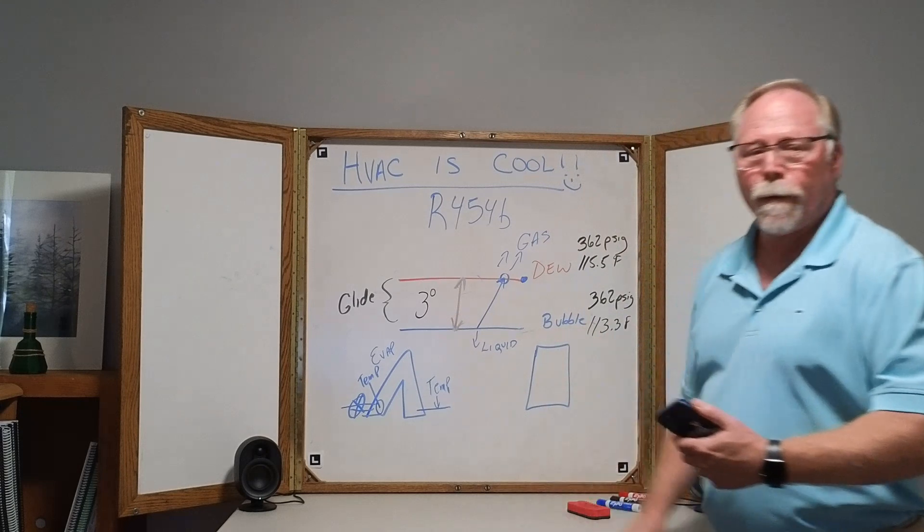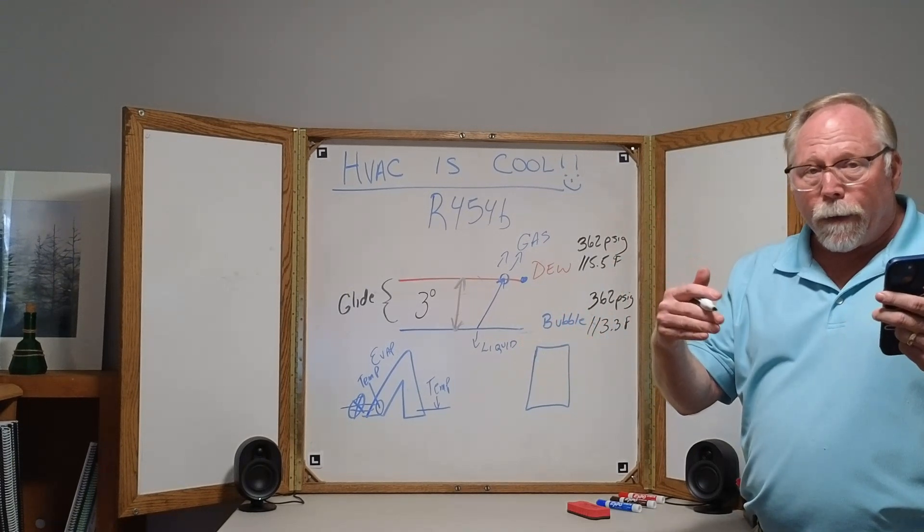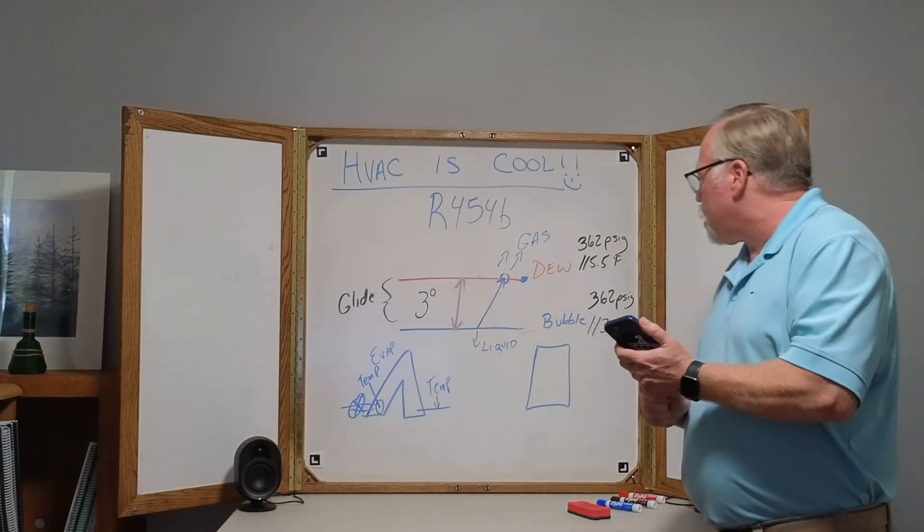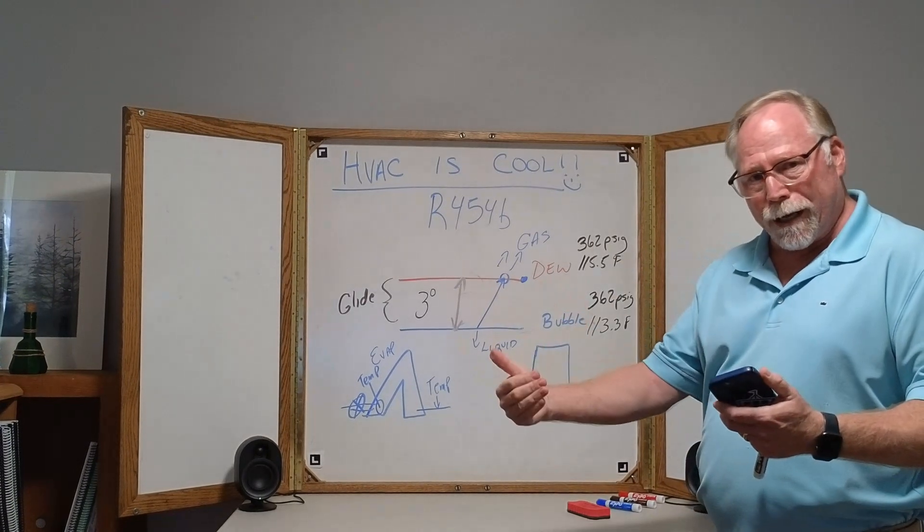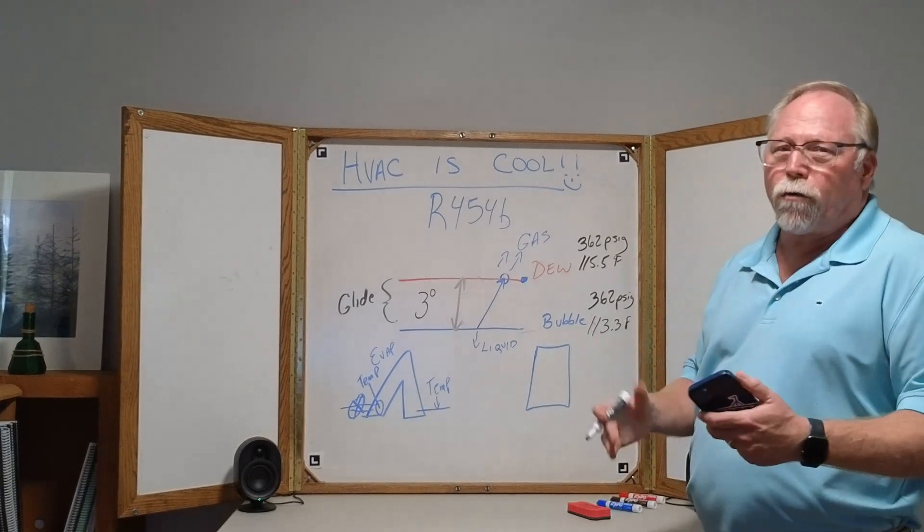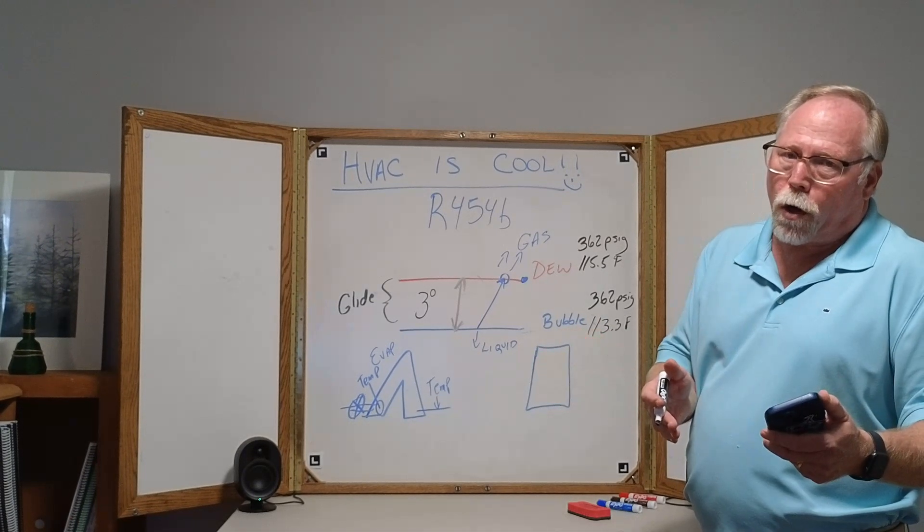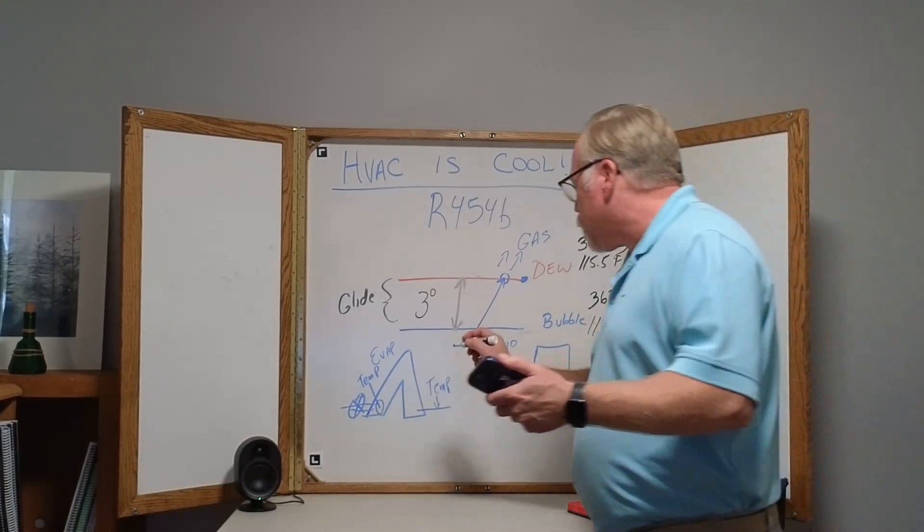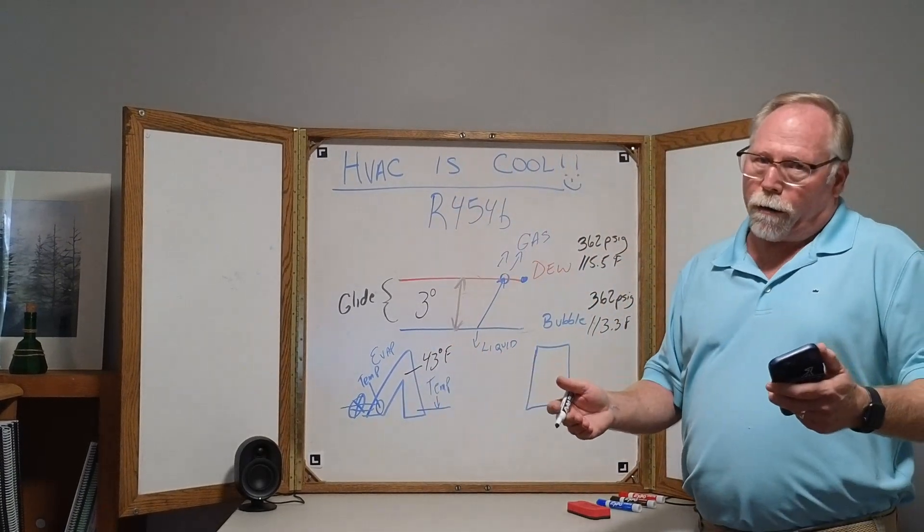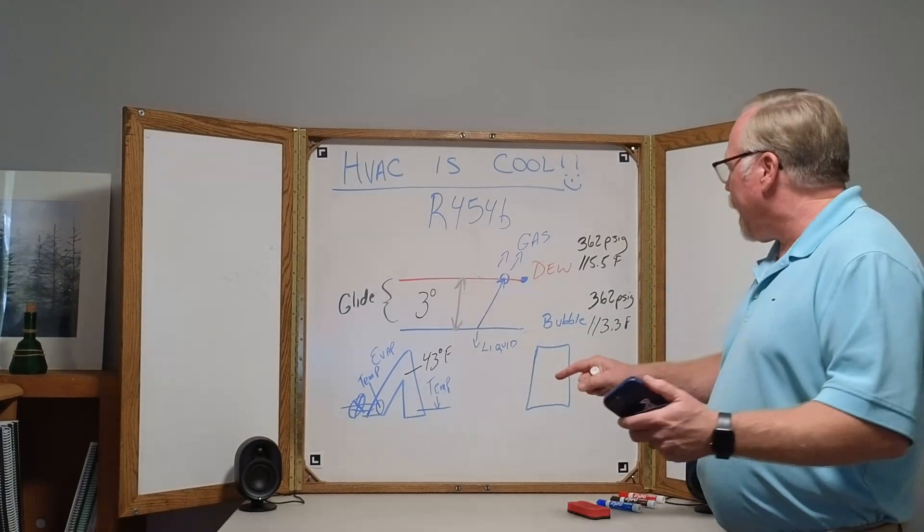So the difference between 115 or say 116 and 113 is three degrees. So there is a three degree glide in between the bubble and the dew. That's all that means. Because we have different refrigerants, they're boiling off and they're condensing at different temperatures. Now what does that mean for you out in the field? No worries at all. In the field we're looking for subcooling leaving the condenser and superheat leaving the evaporator. Over here on our evaporator, we're running roughly about a 45, 43 degree evaporator coil. On the average we're running around 43 to 45 degrees.